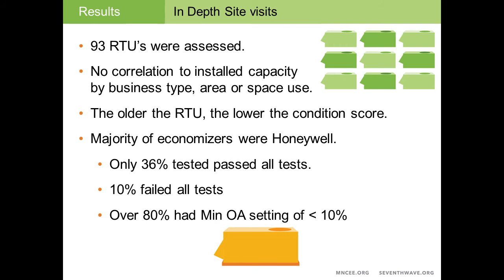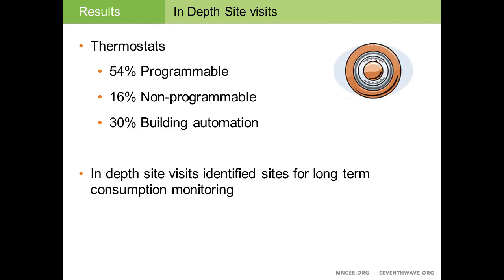One of the things that I did want to mention too was that over 80% of the outdoor air minimum settings for all the rooftop units in the in-depth site visits had a setting of less than 10%. And that's indicative of a lot of rooftop units in Minnesota. 10% is sort of the value that a lot of designers use for outdoor air volumes, but we saw a lot of rooftop units that had 0 for their minimum outdoor air settings. The thermostats that we saw out there, over half of them were programmable. That's a good indicator that there is opportunity there, or at least people are taking opportunity to install these programmable thermostats. There was still a significant amount, around 16% non-programmable, that are just set 24/7, 365 days a year. And then 30% had a building automation system, and this was primarily from one site that had a large number of rooftop units that did have a building automation system.